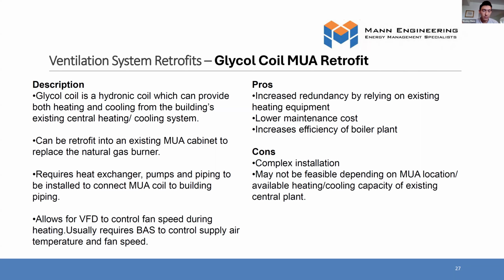You can't have water going through it. It'll freeze. So it's a glycol coil, which means you need a heat exchanger. There's a bit of piping and engineering involved, but depending on the layout of your roof, it could actually be a fairly cost-effective solution where you don't need to replace the whole makeup air unit. It can be refurbished and retrofitted with a hydronic coil, and you can add a VFD, which is great. With these types of projects, we've seen very good custom incentives, up to 75% we've been reaching with our affordable housing clients. So this is a great option.